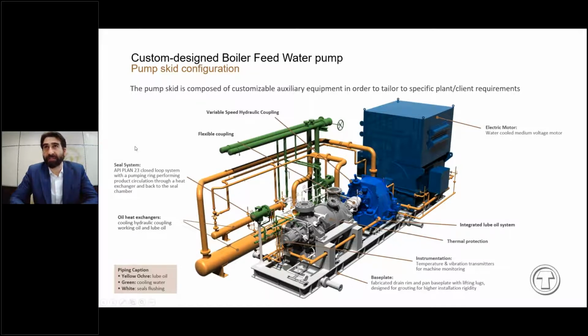The pump is connected to the hydraulic coupling with a flexible coupling, and it is instrumented with temperature and vibration transmitters for the real-time machine monitoring system. All the components are installed on the base plate, which is fabricated, with drain rim and pan, and it is designed for grouting for higher installation rigidity on site.